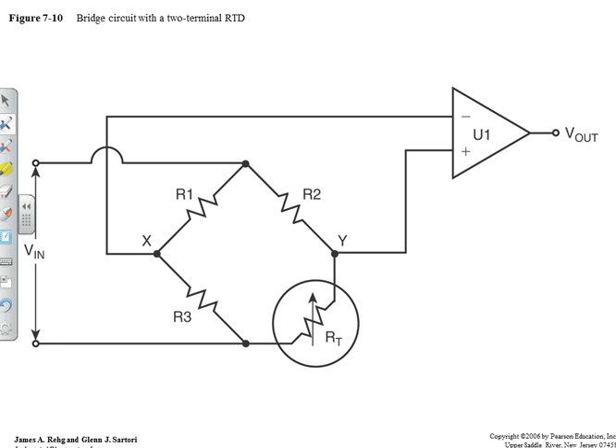When I turn off flow, I'm going to want to know that my core isn't melting down. So I measure the resistance of that resistance temperature device, and then read it on a chart and say, oh, that resistance is 130 degrees.